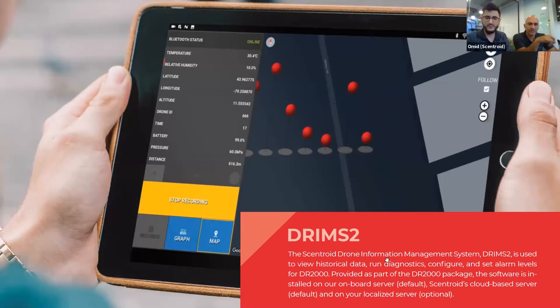There's a question: what is the lifespan of the sensors? Each sensor has a different lifespan. Our electrochemical sensors are warranted for 2 years. Some of them, depending on use - like if you continuously use them in a ground-based system - it will be around 1 to 1.5 years where you need to change it. In a drone, they probably would last the full 2 years.